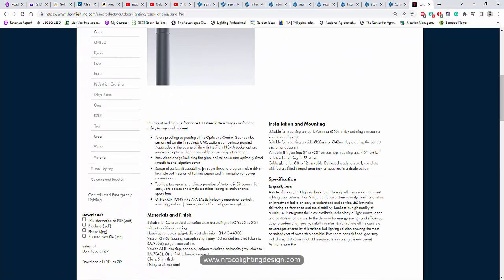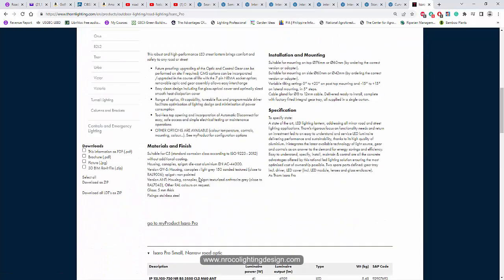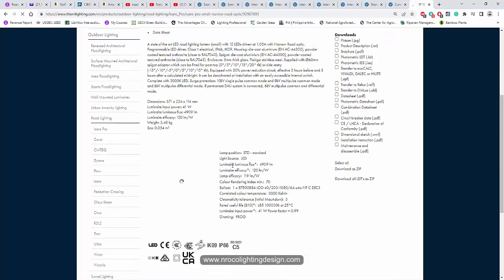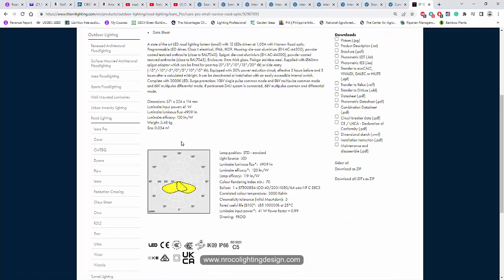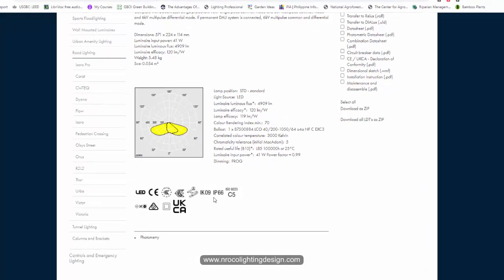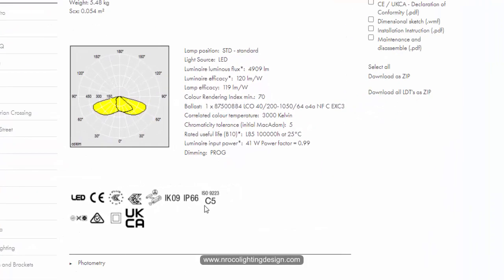It's more higher. So if you use IP66 you can now use 0.91 maintenance factor or the least one is 0.83 as maintenance factor in your road lighting.